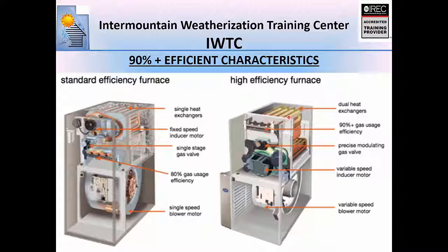Now notice the flue gases have got to be pulled down through the heat exchangers by the inducer motor, and then they're blown out of the flue. So that's another key difference that you'll note. If you just open the door and you see the burners down low, flue up high, well, then it's less than 90%. Burners up high, okay, that's usually an indication that it's a 90% efficient furnace. And it'll have a primary and a secondary heat exchanger.